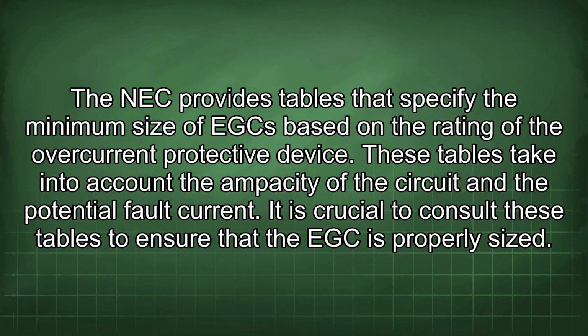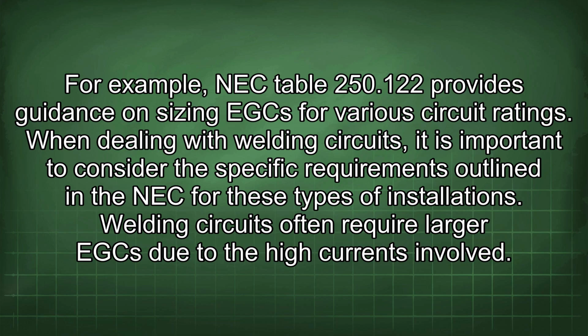The NEC provides tables that specify the minimum size of EGC based on the rating of the overcurrent protective device. These tables take into account the ampacity of the circuit and the potential fault current. It is crucial to consult these tables to ensure that the EGC is properly sized. For example, NEC Table 250.122 provides guidance on sizing EGC for various circuit ratings.